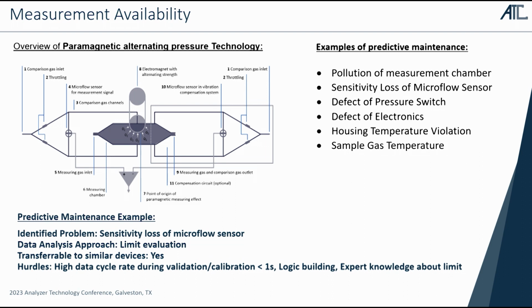We see that there are many topics which you can really address already by pulling out this data and evaluating it. So typical issues we see: we have pollution in the oxygen measurement, in the measurement chamber. We see sensitivity loss of various sensors, in this case a microflow sensor, defect of pressure switch, defect of electronics, problem with the housing temperature, and so on. And one of the examples we had is the sensitivity loss of the microflow sensor.